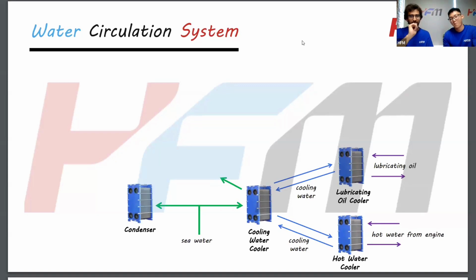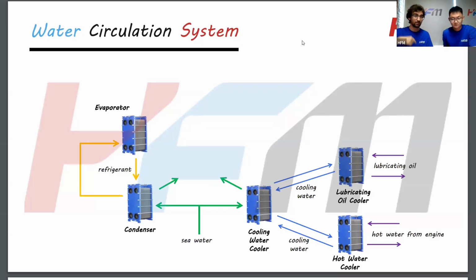Now I want you guys to pay attention to this one. You're going to have a condenser that's going to interact with the seawater as well. This condenser is going to react with a refrigerant, which exchanges heat with the seawater and goes to an evaporator. In this evaporator, it exchanges energy with the chilled water.